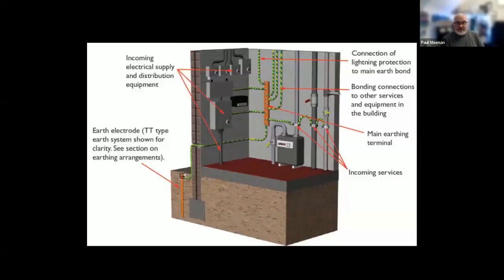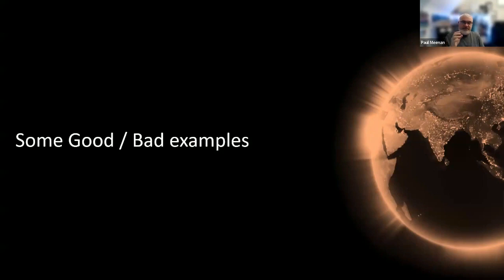So how do we do it? Well, we basically bond everything together with a bit of green and yellow cable. So that is a cross-section of an installation where you have the incoming supply cable, the main switch, and a copper earth bar, and we bond gas, water, other services, ductwork, and sometimes, depending on the earthing, we put electrodes in. There is a requirement or a recommendation now for new installations to have electrodes. That wasn't necessarily the case in the UK. So that's just some fundamentals there on the terminology.